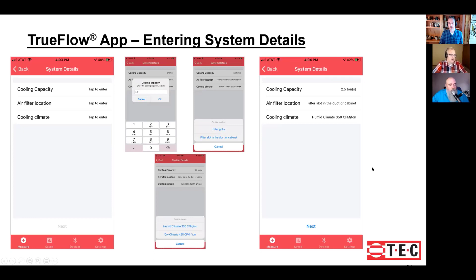So you give it that information, and then you're going to tell it which direction the airflow is. Is this an upflow system, downflow system, or is it horizontal? And that's really to help you orient the system in your head, so that the prompts on screen are going to help you figure out where those probes should go in your system, give you a little better visual cues to help you out there. So then you actually start making the measurements. The screen shows the manometer there, and you just really look at the green tube there, and that'll tell you where in the system that measurement should be made. So the first measurement here is in the return duct. You put the tube into the return duct before the filter, and then you click take a measurement. And you repeat that process, 2 to 4 times, depending on what type of system. There's going to be 2, 3, or 4 pressures. And you take the different pressures, then you hit continue. And then the next step we didn't show here is to put the TrueFlow grid in and take the flow measurement. And then once you complete that, you get the report.